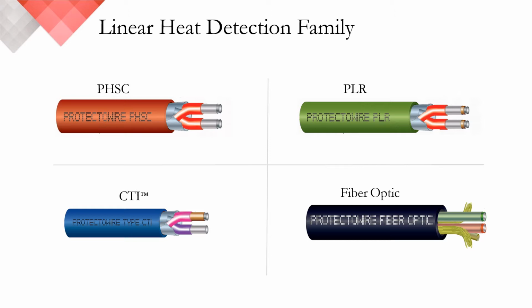Next is the PLR series, which stands for Protectowire Low Resistance. Same construction as PHSC, the PLR series adds copper-coated conductors to reduce the cable's overall resistance value from 0.185 ohms per foot, which is the standard resistance value for steel, to 0.058 ohms per foot. That's a roughly 2/3 reduction in resistance value. And in this case, lower resistance means longer runs.